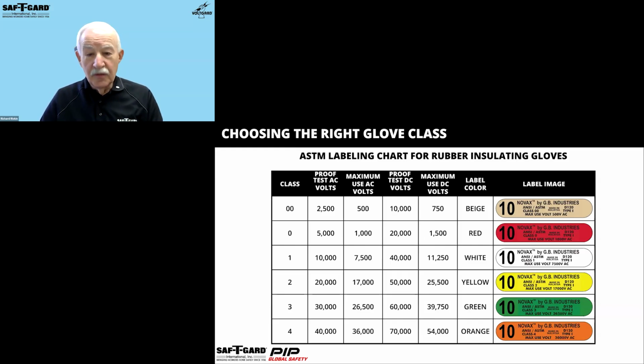Rubber insulating gloves are available, as you can see on the chart, in 6 specific voltage classes from 00 through class 4, categorized by the level of voltage protection they offer. They'll also generally indicate if they're a type 1 or type 2 glove, type 1 being normal rubber insulating gloves. Type 2 gloves are rated for their resistance to ozone. That voltage protection is broken down into these classes, and each class of gloves, as I said, is clearly marked with the maximum use voltage, AC, and this is all on that permanent color-coded label.